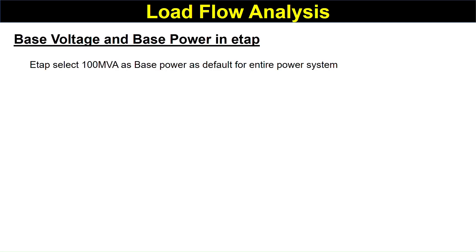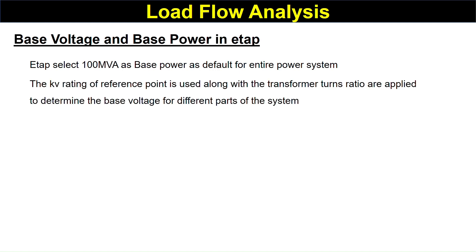Now, how do we select the base voltage and base power in the ETAP system? ETAP selects 100 MVA as the base power by default for an entire power system. The kV rating of the reference point is used along with the transformer's turns ratio to determine the base voltage for different parts of the system.